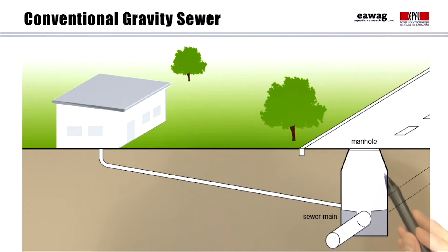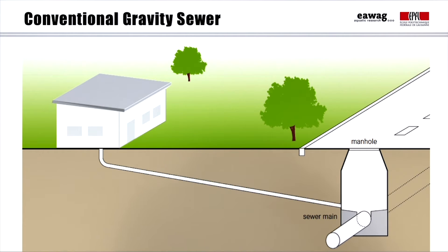Access manholes are placed at set intervals above the sewer, at pipe intersections and at changes in pipeline direction. When the sewer also conveys storm water, which is known as a combined sewer, sewer overflows are required to avoid hydraulic surcharge of the treatment plant. However, nowadays a separate drainage system for rainwater, or local retention and infiltration, are recommended instead, which leads to cheaper and more efficient systems.